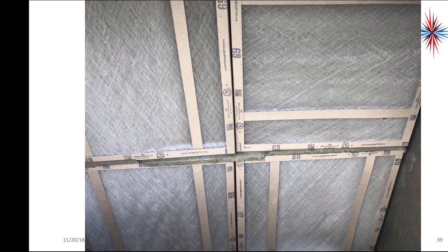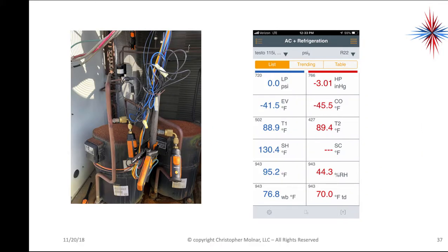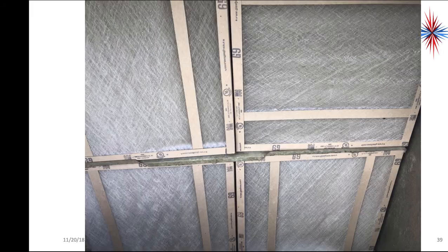Went around to the filter side. Okay, now here's where I'm starting to look for a leak. Okay, I have 0 psi in a refrigerant circuit. I really need to find out where it is. Okay, I didn't carry a tank of nitrogen onto the roof, so I wanted to pull the filters and check the evaporator. You'll notice the sides of this evaporator coil are in pretty bad shape.